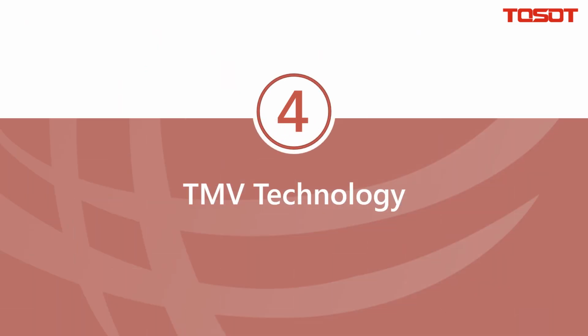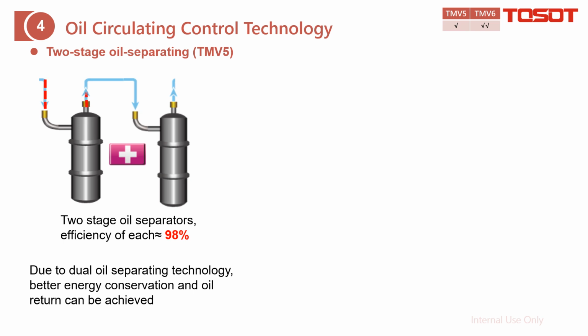TMV technology. Oil circulating control technology. First, let's focus on GMV5, as we apply two oil separators, which means two-stage oil separating, and the efficiency can be as high as 99.9%. And just for this reason, as we can separate more oil, we can also prolong the oil return period, which saves energy.